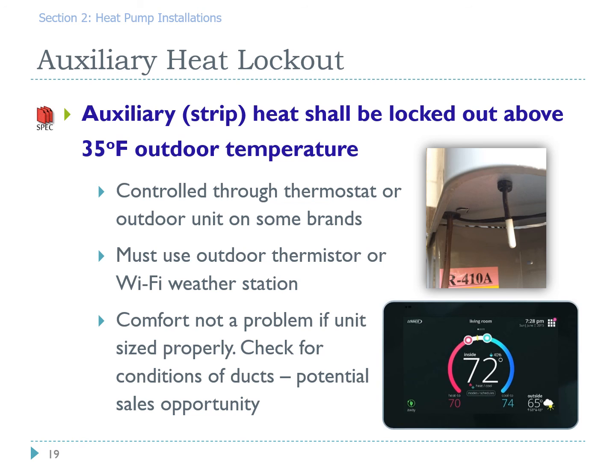Comfort won't be an issue if the unit's sized properly to be able to heat the home all the way down to 30 degrees. Locking that strip heat out at 35 and above won't cause a comfort issue. For ducts outside the conditioned space in an attic or a crawl space, you might want to check the condition of those because that could influence your sizing. But we look at these as potential sales opportunities to be able to add this extra functionality.